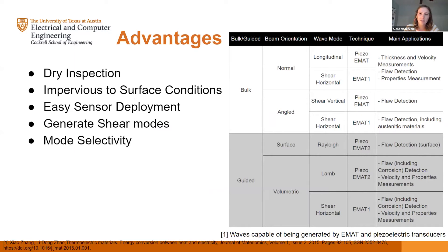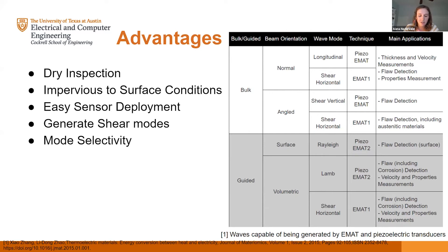The advantages of using an EMAT compared to a piezoelectric transducer: first, you don't need a couplant for transmitting sound. This makes it great if you're working with something very hot or very cold, because you don't have to deal with evaporation or freezing. It can also be integrated into automated environments more easily, since you don't have to apply and then clean up the couplant, making the process quicker. Additionally, you're impervious to surface conditions — you don't have to deal with roughness, oxidation, or pollutants.